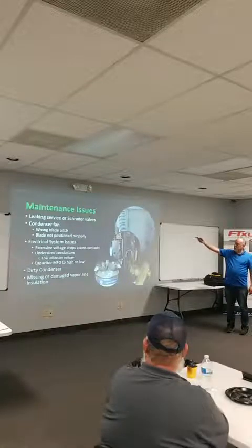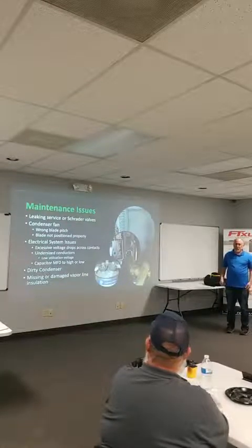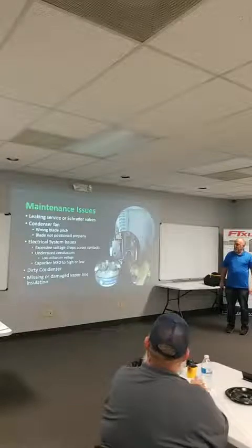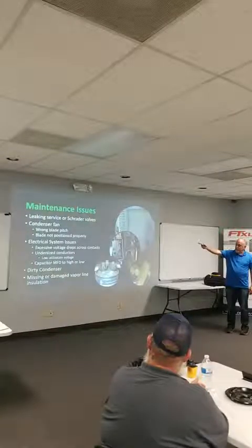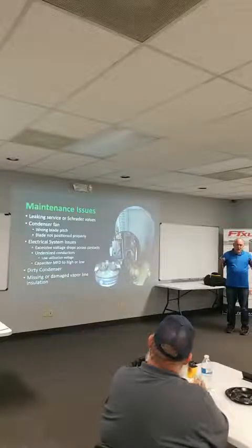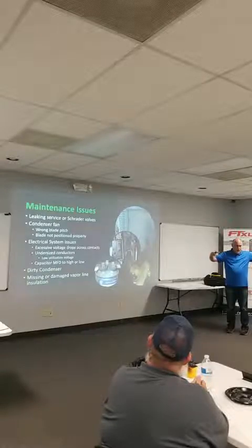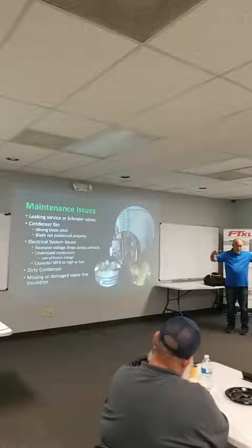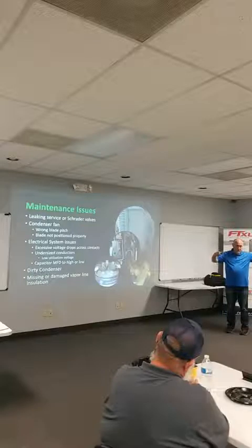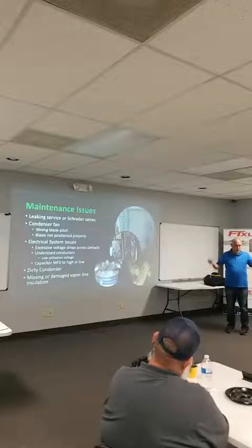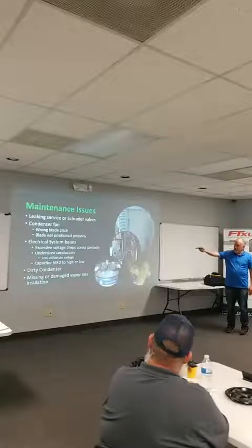Look at the condenser coil. You've all seen Trane condensers, especially the split ones, where it gets so packed in between the coils, right? Condenser fan blades improperly pitched or positioned incorrectly. How many times have I seen guys put in a new condenser fan motor? You know what a volute is, right? There's the center of the hole that the fan resides in. It's got to ride the center of that volute. Otherwise, the air is going to go through the fan improperly and you're going to get high head pressure.